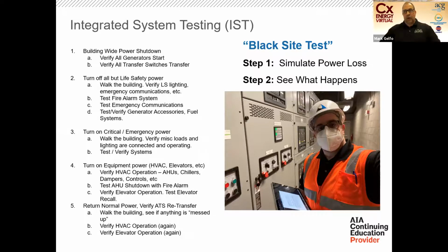Then walk the building and make sure that things on that life safety branch are actually working, that the egress lighting is working, that the fire alarm is working, that the fuel pumps for the generator are actually connected to that branch of power, and that they're working properly. Then add on the branches of power from most critical to least critical, walking the building each time to make sure what's connected to what's supposed to be connected actually is, and that they're operating correctly.